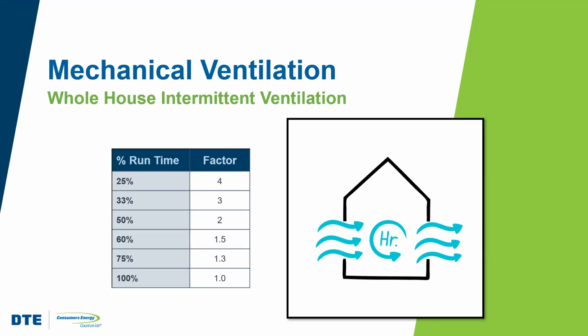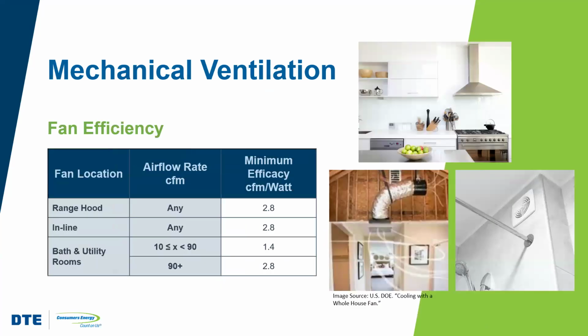So for example, if the system were to run at only 25% of the time, then the intermittent ventilation rate would have to be 4 times the continuous rate. If the system were only to run 75% of the time, then the intermittent ventilation rate would have to be 1.3 times the continuous rate. Additionally, a good design will specify and ensure that the ventilation fans used are energy efficient and that they have performance labels indicating that they meet the minimum efficacy requirements that the code inspector is going to be looking for.